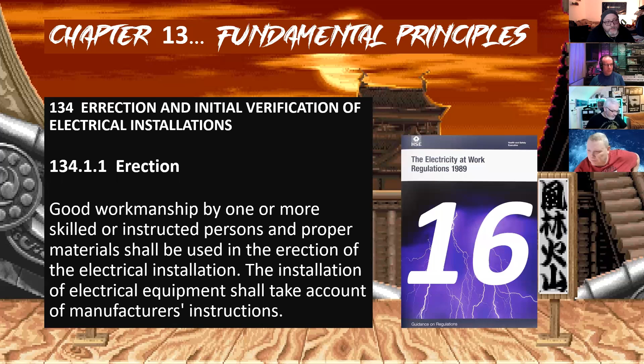Yeah, so good workmanship material. This is the second, in my opinion, most breached regulation in 7671. Because it used to be, I think it was 133.0.1.01 originally in the 16th edition, when it was the dashes, and it used to be good workmanship material should be used by competent persons in the erection of an electrical installation, or words to that effect. Now it's changed to this because the word competency is a requirement of the law, so they've removed competency with the exception of inspection and testing.